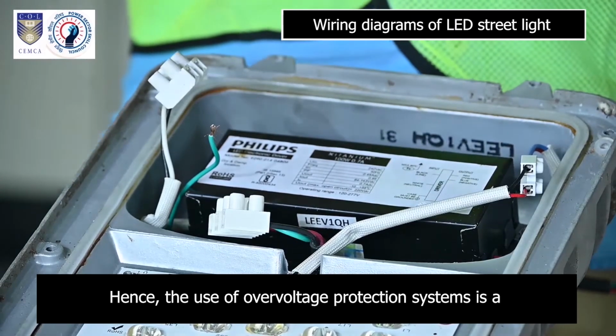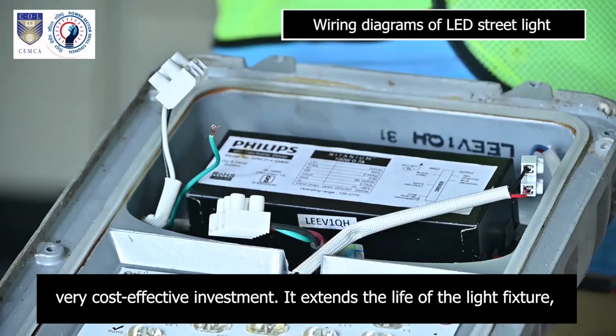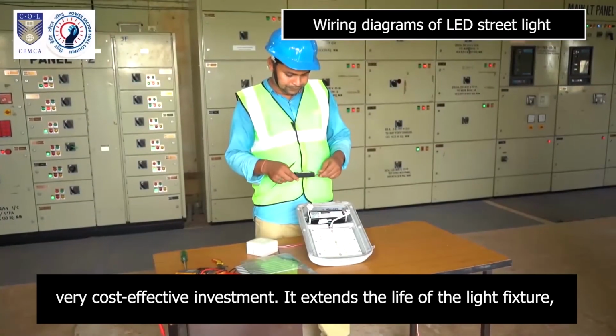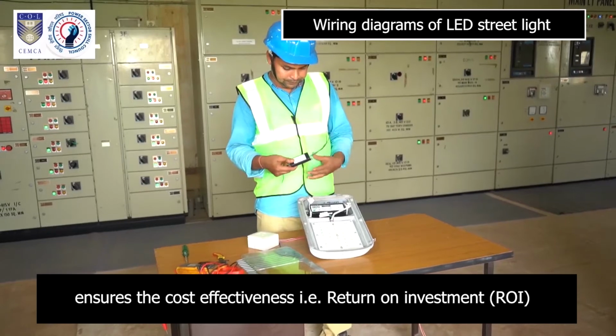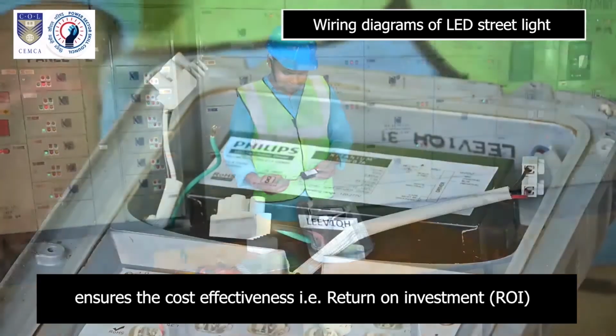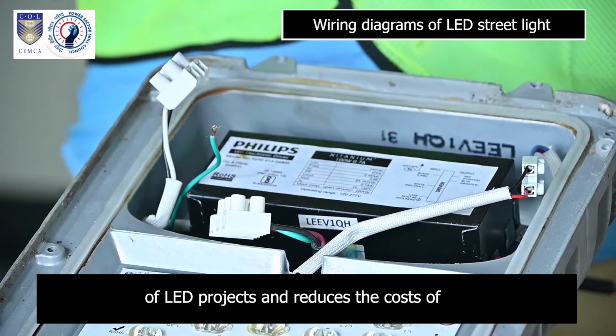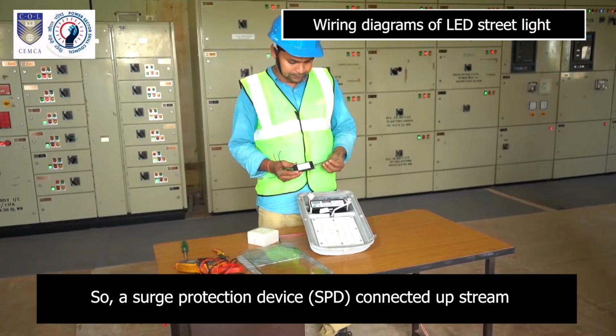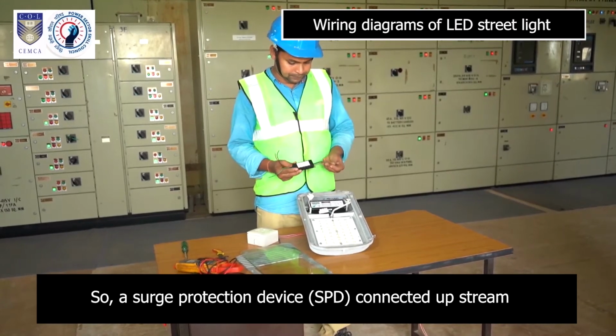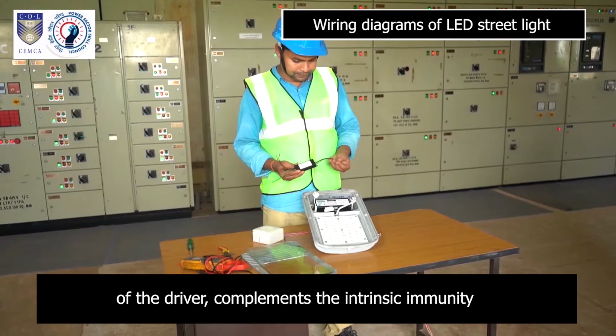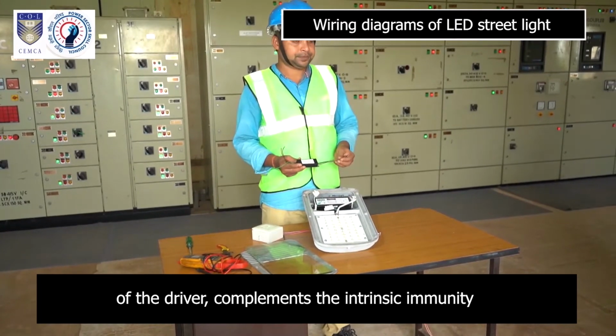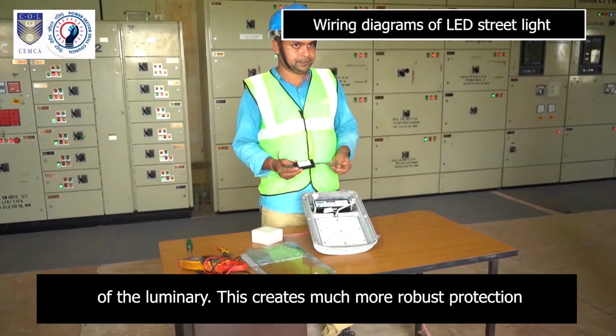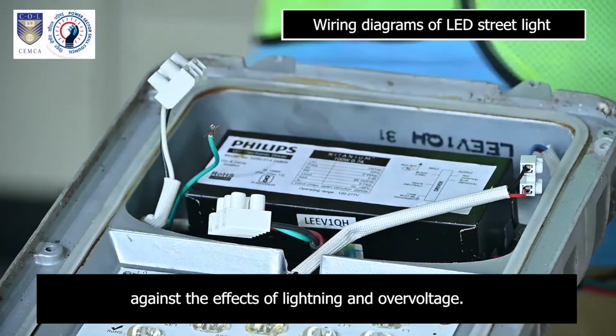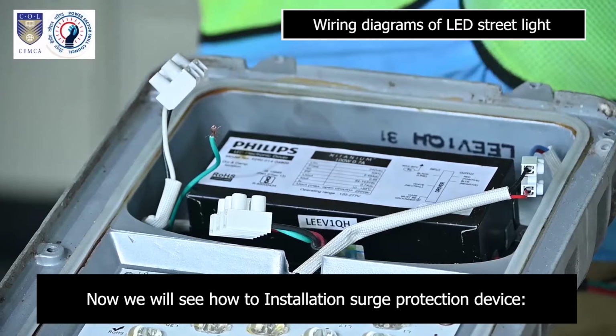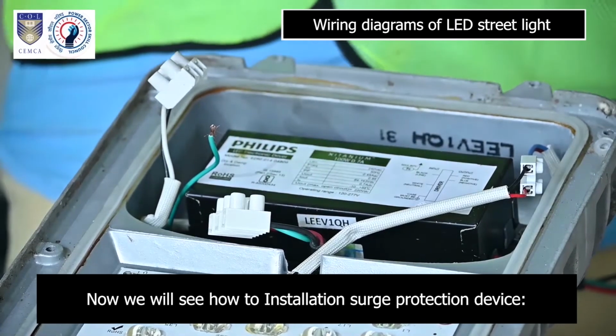The use of overvoltage protection systems is a very cost-effective investment. It extends the life of the light fixture, ensures the cost effectiveness, that is return on investment, ROI, of LED projects and reduces the cost of maintenance and replacement of light fixture. So, a surge protection device SPD connected upstream of the driver complements the intrinsic immunity of the luminaire. This creates much more robust protection against the effects of lightning and overvoltage. Now we will see how to install surge protection device.